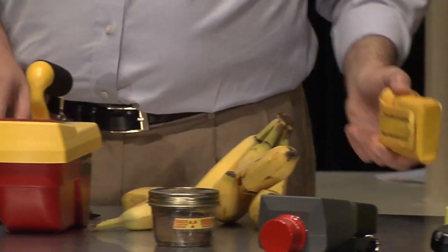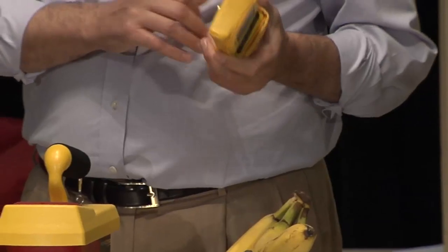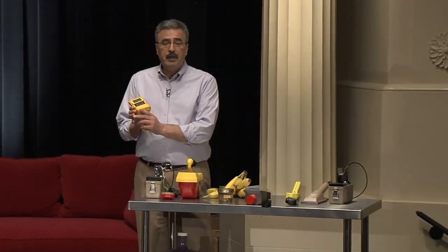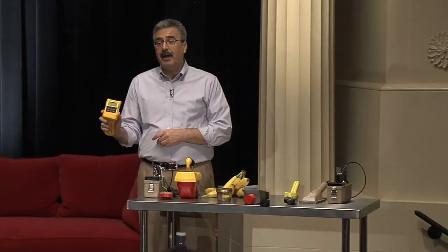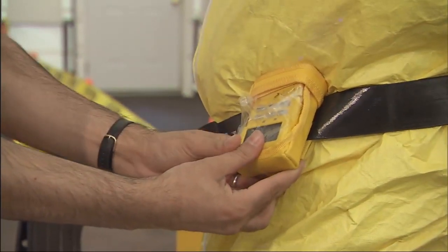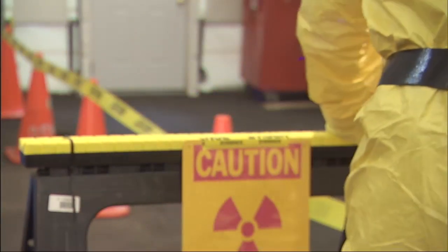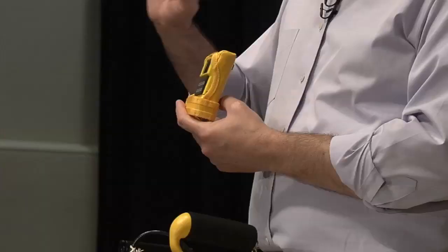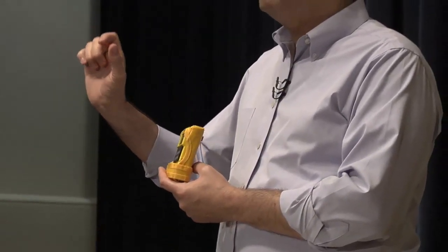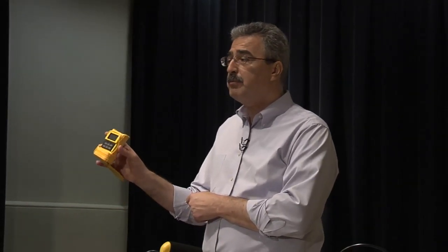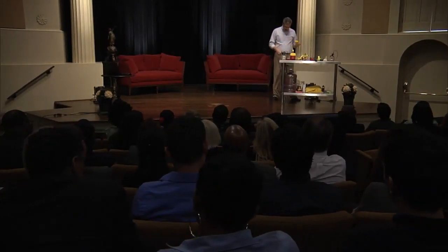And this instrument is particularly useful for first responders. It's an alarming dosimeter. These alarming dosimeters report radiation dose in real time. So it would allow the first responders to identify whether they approach an unsafe area where the radiation levels may be high, or if they reach a pre-selected dose level, so they won't exceed their allowed dose. They're very useful instruments, and radiation safety officers may use these to monitor a worker's dose. So it's very useful for first responders.